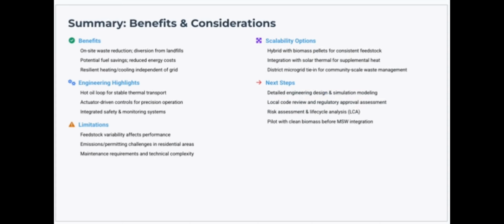And the summary of benefits and considerations. On site, the benefits would be waste reduction, diversion from landfills, potential fuel savings, reduced energy costs, resilient heating/cooling independent of grid. Engineering highlights: hot oil loop for stable thermal transport, actuator driven controls for precise operation, integrated safety and monitoring systems. Some of the limitations the system may have are feedstock variability, which affects performance, and emissions/permitting challenges in residential areas. Say if it's a tight area, it might not work the best in apartment complexes and stuff like that, or just densely populated areas.